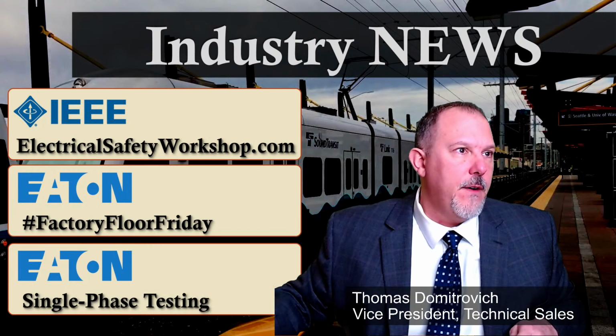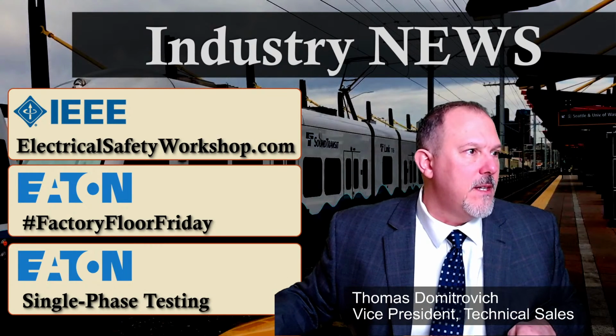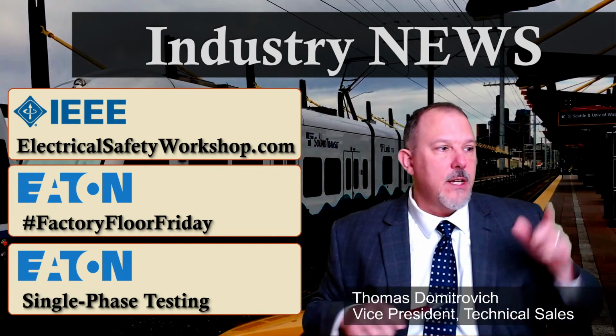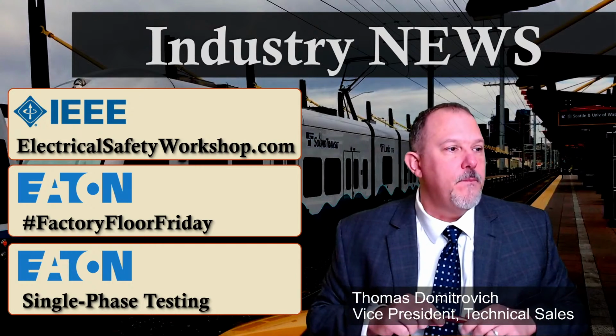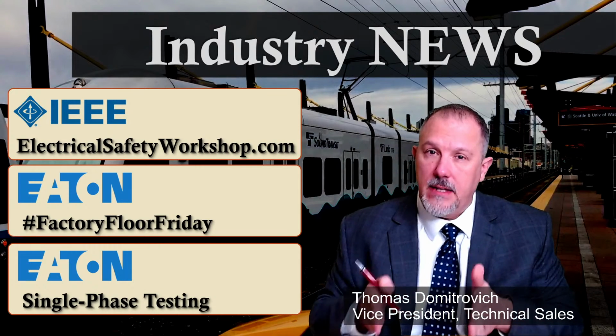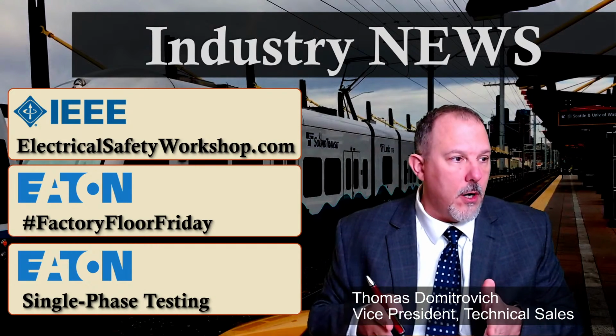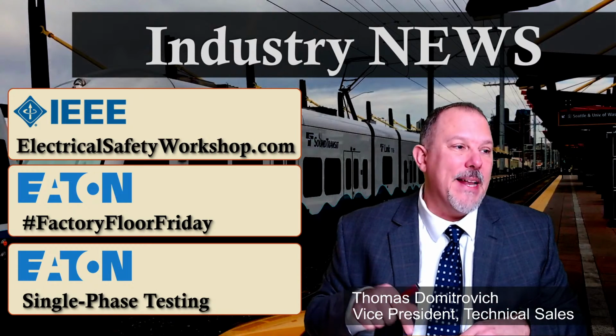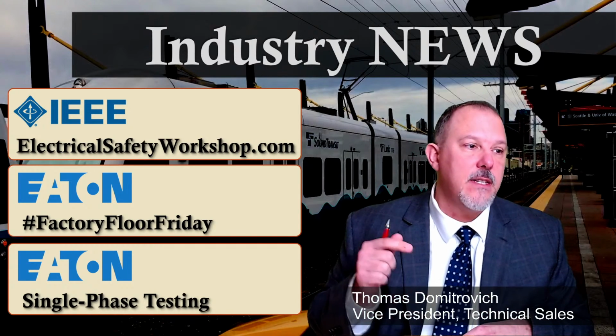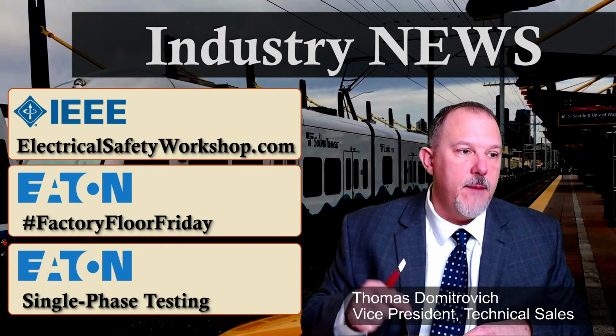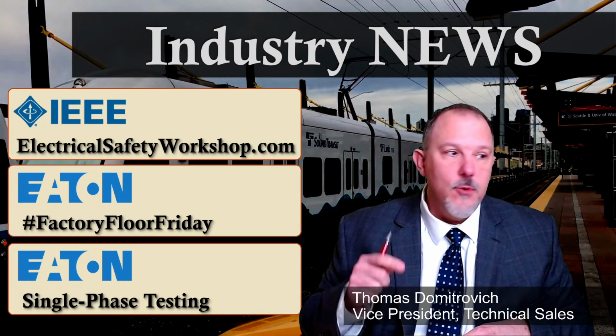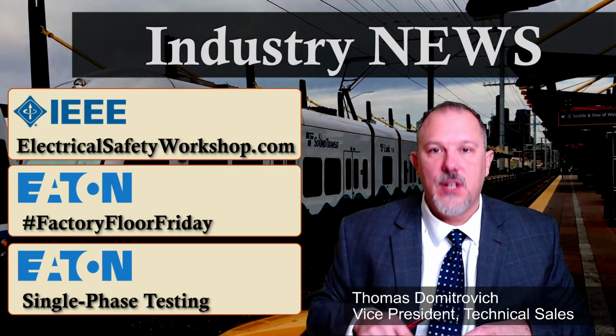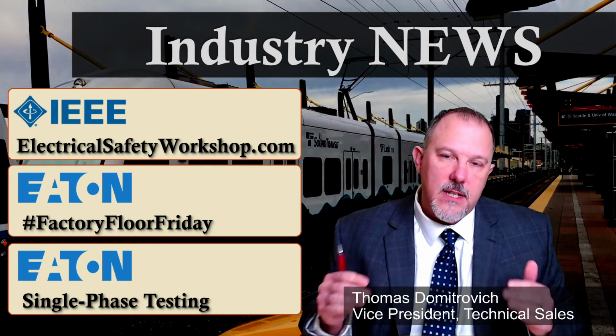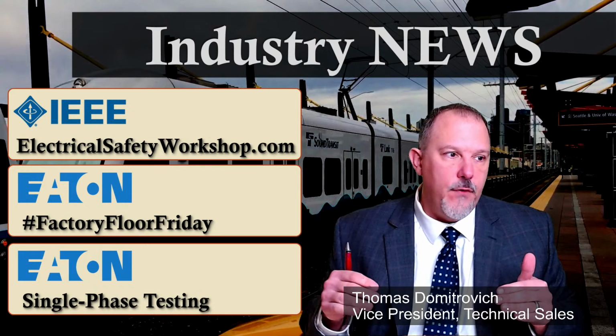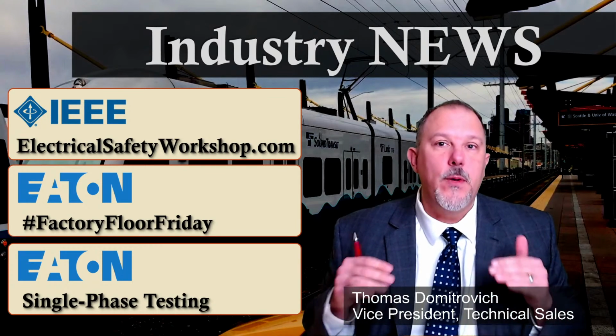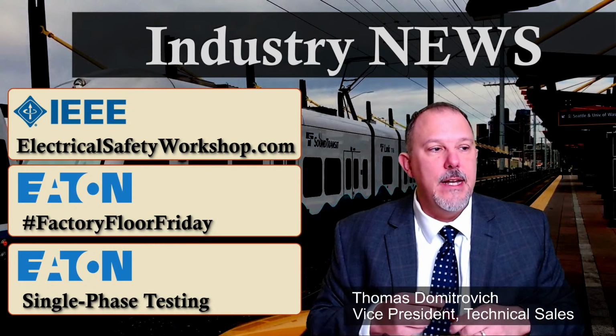In 1584 itself, I believe... yep, there it is. Section 4.3 of 1584 tells us for a three-phase system, sustainable arcs are possible but less likely in three-phase systems operating at 240 volts nominal or less, with an available short circuit current less than 2,000 amps. So that helps us establish a floor for three-phase, but we don't have anything for single-phase.